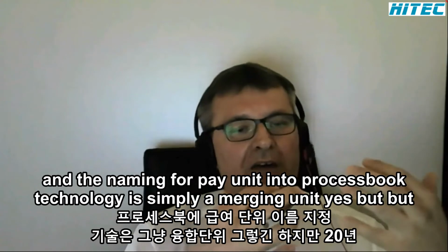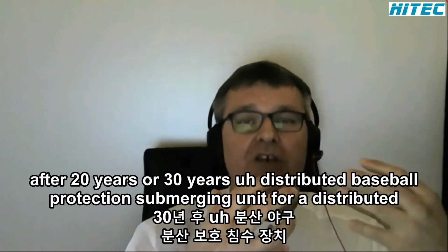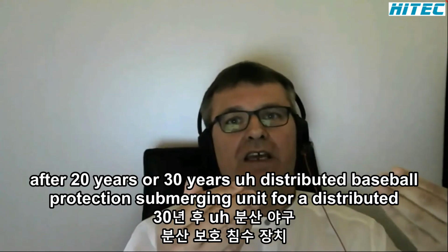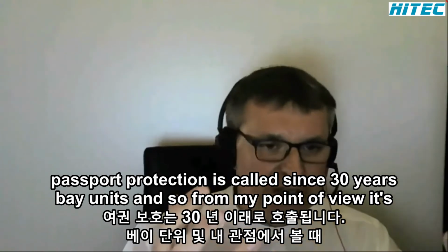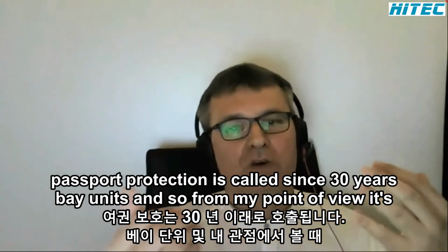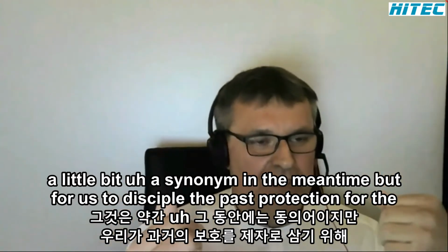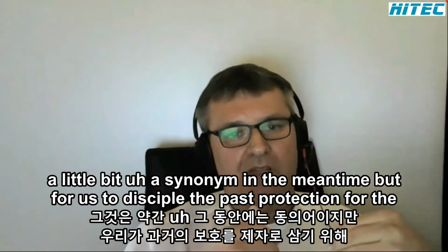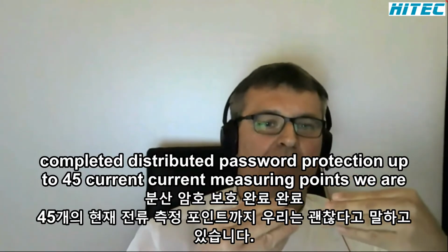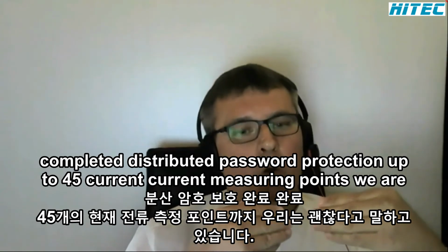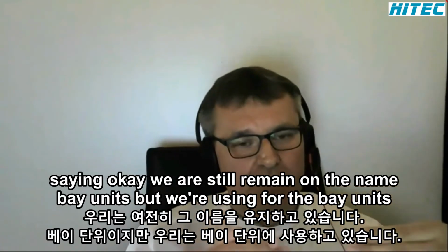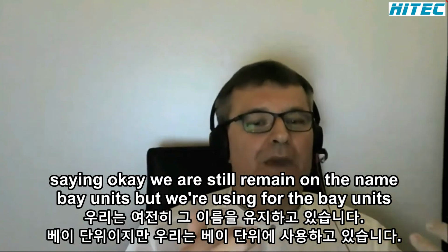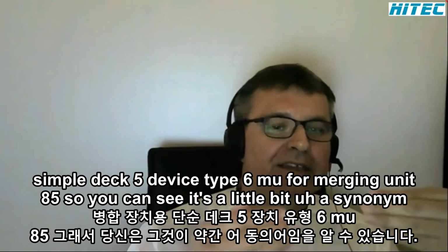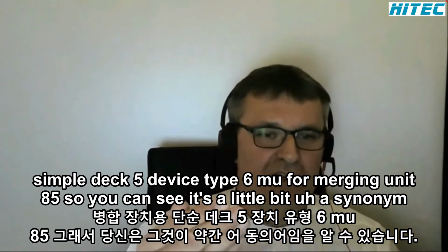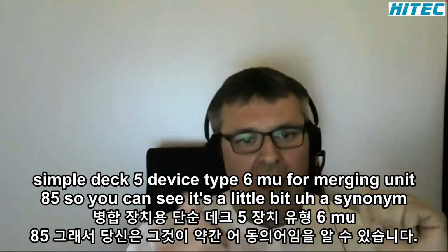Yes, but after 20 years or 30 years of distributed busbar protection, the merging unit for distributed busbar protection has been called bay unit for 30 years. So from my point of view, it's a little bit a synonym in the meantime. But for the completed distributed busbar protection up to 45 current measuring points, we are saying, okay, we still remain with the name bay units, but we're using for the bay units the SIPROTEC 5 device type 6MU85 merging unit. So you can see it's a little bit a synonym.